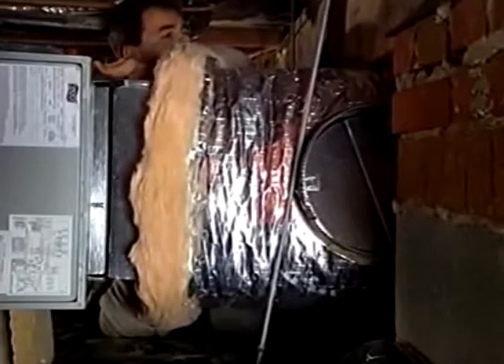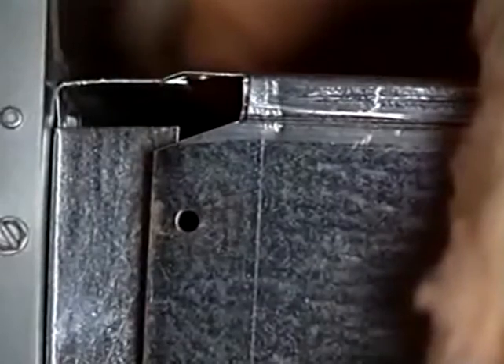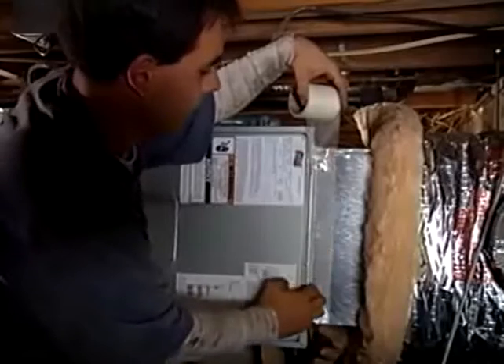Okay, I'll put this side here on first. If it's your job to make the plenum connection to the air handler, taking extra care to seal this connection is extremely important. It is here that much of the air leakage can take place. Proper technique starts from the moment the connection is made. You can see these small gaps at the corners can be potential sources of air leaks. This contractor first seals these small gaps with a UL 181 foil tape. He then uses a fiberglass mesh tape around the entire connection. Finally, he paints this surface with mastic.